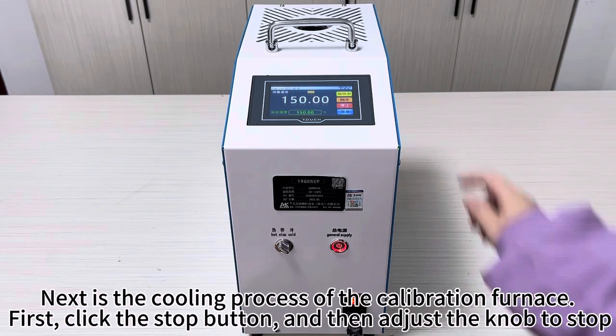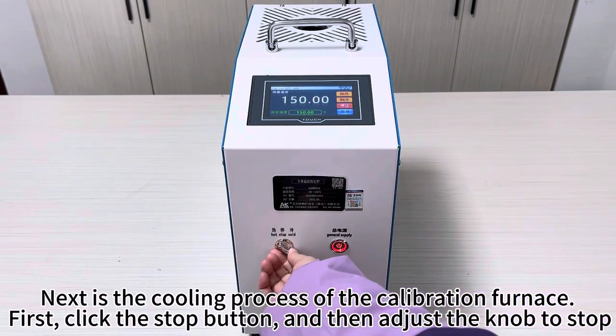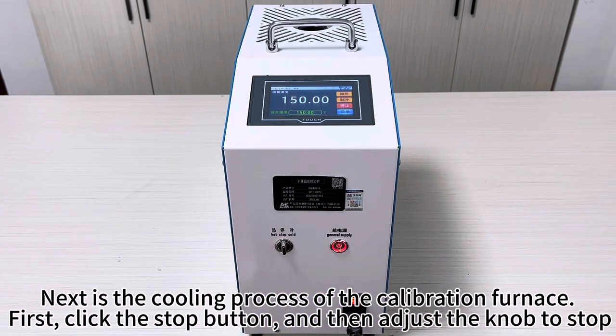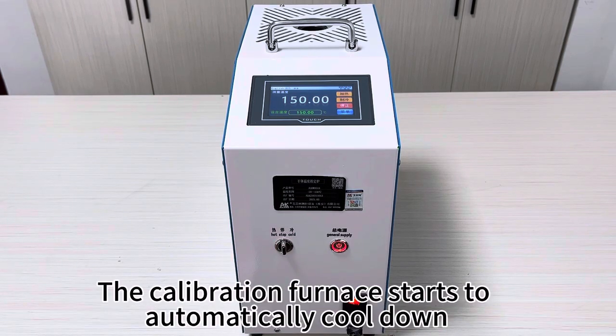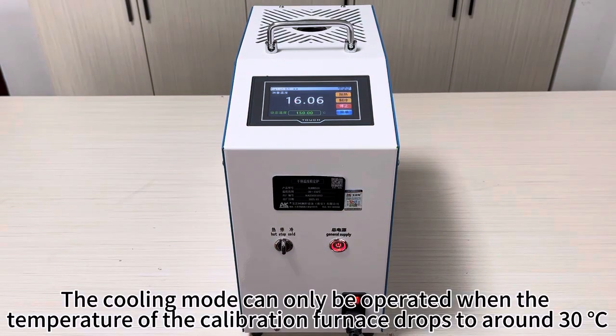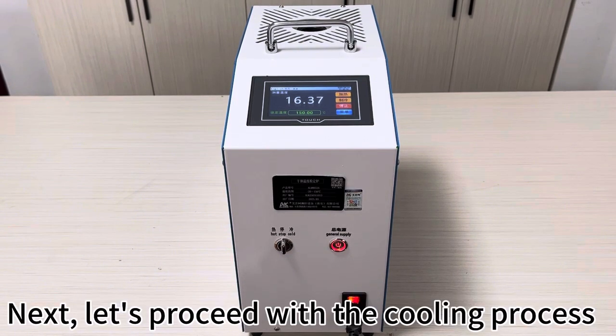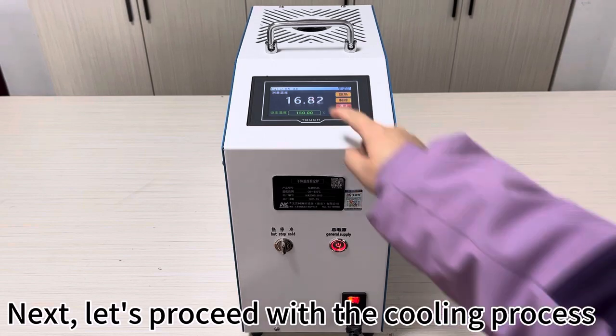Next is the cooling process of the calibration furnace. First, click the stop button, and then adjust the knob to stop. The calibration furnace starts to automatically cool down. The cooling mode can only be operated when the temperature of the calibration furnace drops to around 30 degrees Celsius. Next, let's proceed with the cooling process.